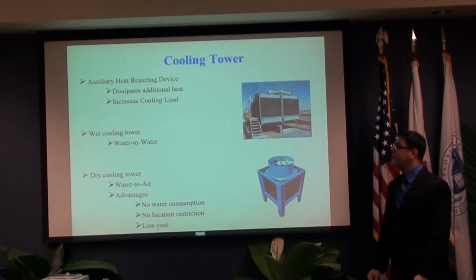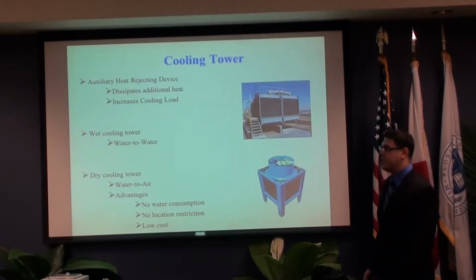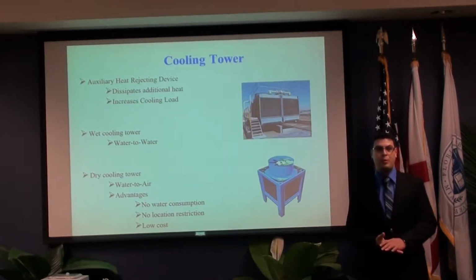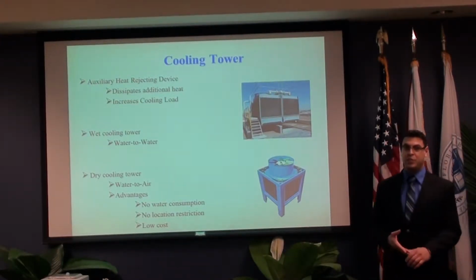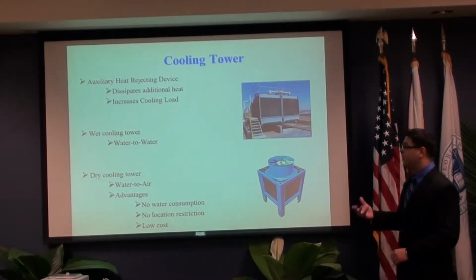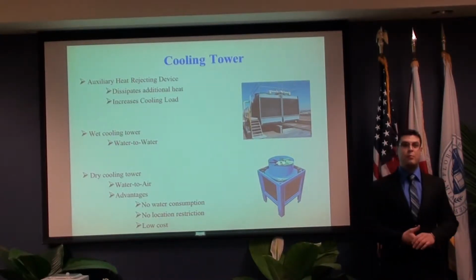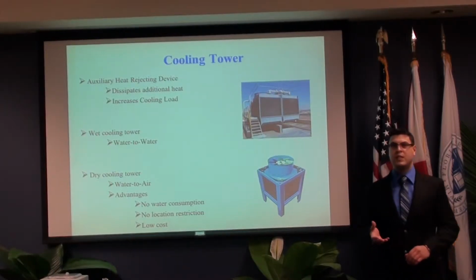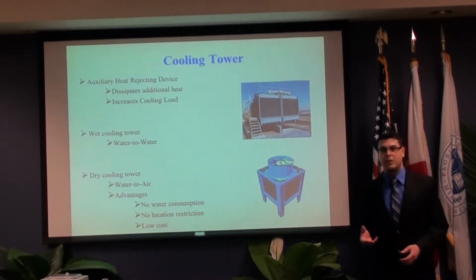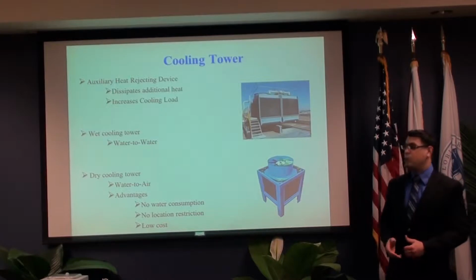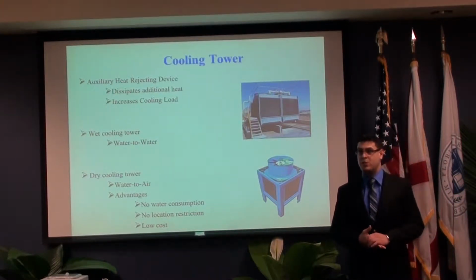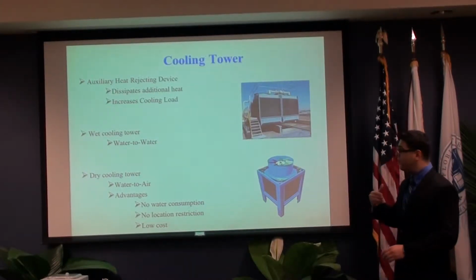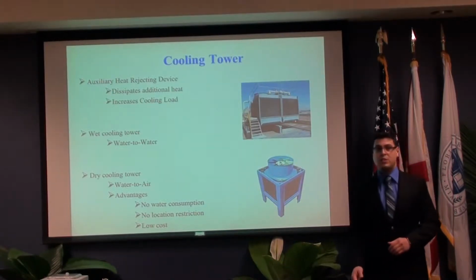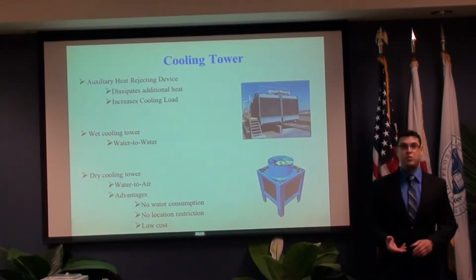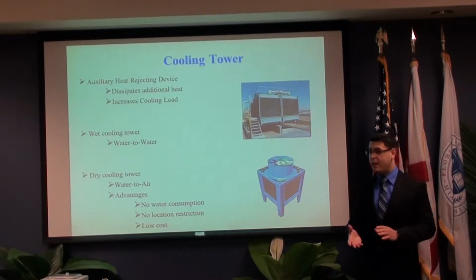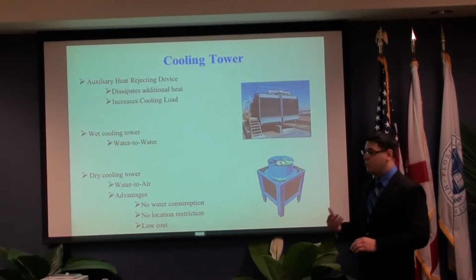A cooling tower is an auxiliary heat rejecting device that can be connected to a geothermal heat pump in order to dissipate additional heat. In doing so, it's going to decrease the cooling load, and there are two commonly known types of cooling towers: the dry cooling tower and the wet cooling tower. The wet cooling tower is a water-to-water heat exchanger that uses the evaporation method to dissipate heat, and the dry cooling tower is a water-to-air heat exchanger that uses ambient air and convection to remove the heat.